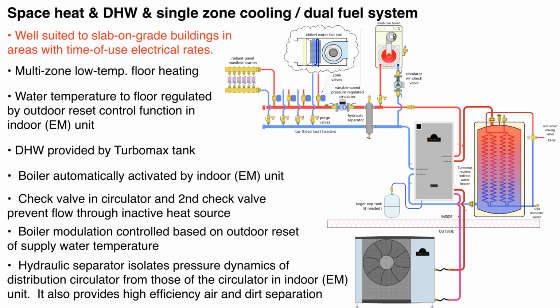Now, if the boiler is operating, I'm showing a circulator with a built-in check valve. It is important that you have a check valve in any situation where you have parallel pumps. You don't want one pump creating flow in reverse through a circuit that has a circulator, but the circulator is off. So if this circulator is on, that flow comes out and it cannot go backwards because of this check valve right here. And vice versa. If the heat pump is providing flow through here, we cannot induce a reverse flow because in this case, we have a check valve built into the circulator.